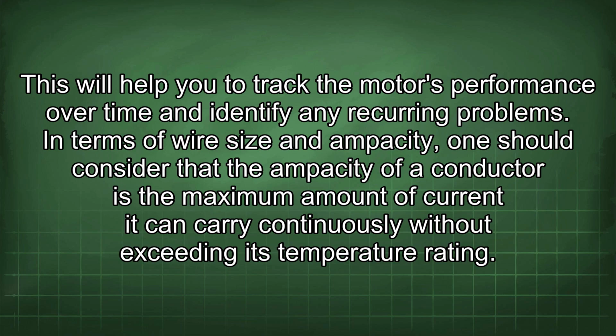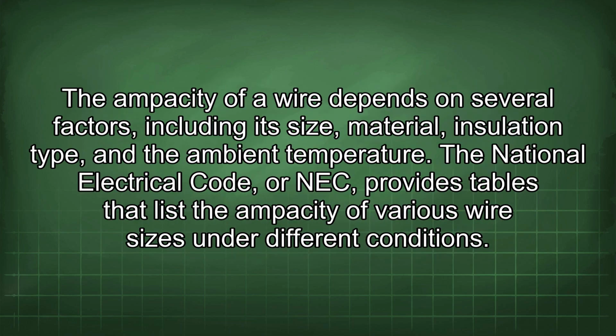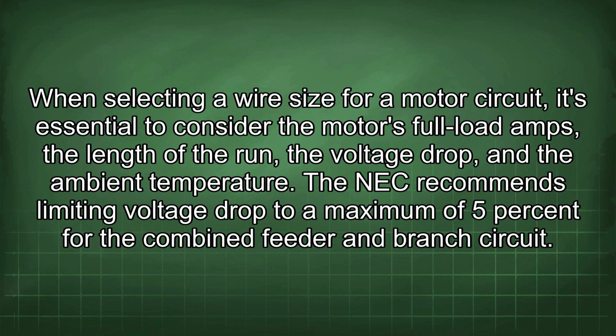In terms of wire size and ampacity, one should consider that the ampacity of a conductor is the maximum amount of current it can carry continuously without exceeding its temperature rating. The ampacity of a wire depends on several factors, including its size, material, insulation type, and the ambient temperature. The National Electrical Code, or NEC, provides tables that list the ampacity of various wire sizes under different conditions. When selecting a wire size for a motor circuit, it's essential to consider the motor's full load amps, the length of the run, the voltage drop, and the ambient temperature.